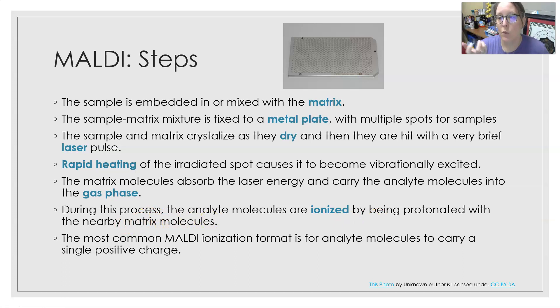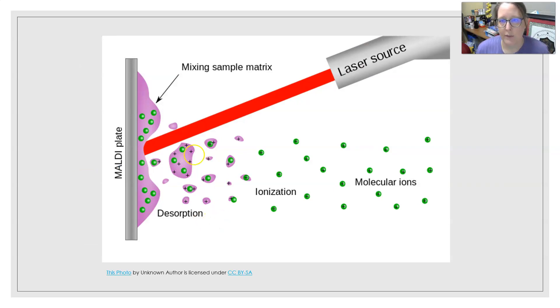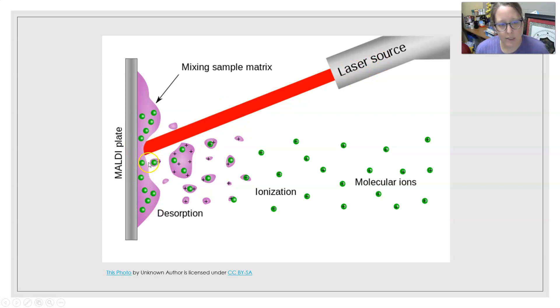During that process, the analyte molecules are ionized by being protonated with the nearby matrix molecules — the matrix molecules are what's getting charged and helping the molecules go into the gas phase, and as that's happening, the matrix molecules are donating the charges — the protons — to the molecules of the sample. The most common MALDI ionization format is for an analyte molecule to carry a single positive charge. In the graphic, the matrix (shown in pink) is mixed with the sample (green dots), hit with a laser, rises off the plate into a gas phase, donates protons to the sample molecules, and the sample molecules become charged or ionized and enter the mass spectrometer.